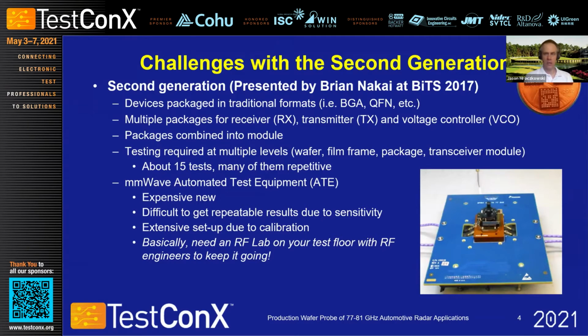Then after these devices were tested individually, they were put into a module and tested at that. Ultimately, throughout the entire test process, there ended up being about 15 tests that were done at the various levels of integration. And many of these tests were repetitive because each time you added a layer onto the device, you had to test the quality of it. And so, there were tests done at wafer, there were tests done at film frame, at package, and then even afterwards at the transceiver module level.